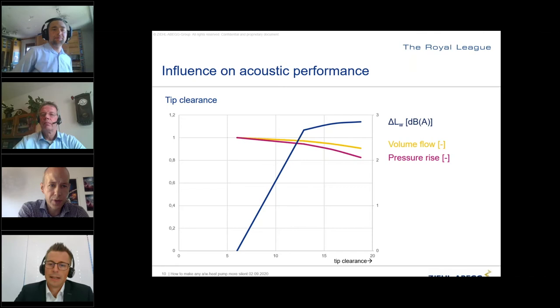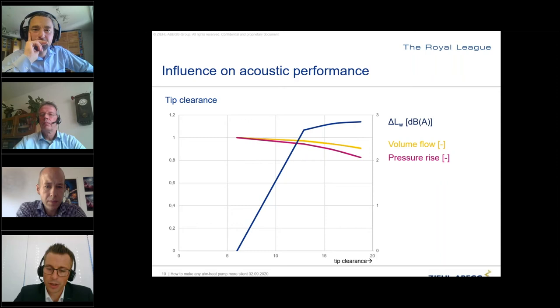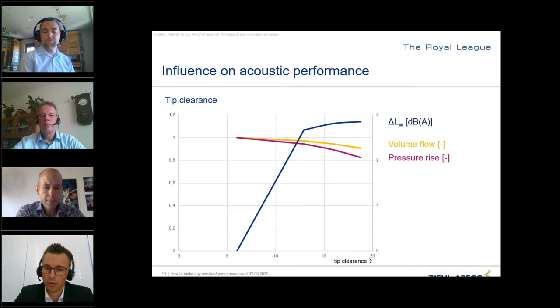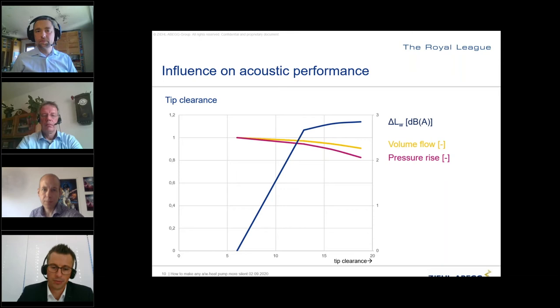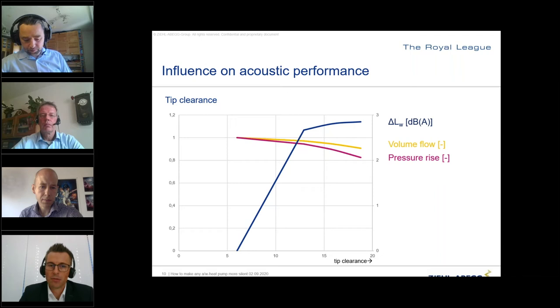If you go for a bigger tip clearance to avoid icing of the fan, then the fan gets louder, up to 3 dB. You have some influences on volume flow and pressure rise as well, which are negative, depicted in yellow and pink here. There are even some systems on the market which state they don't have any tip clearance, but even there's some clearance between the rotating and the steady part, and there can be icing during the defrosting cycle as well.